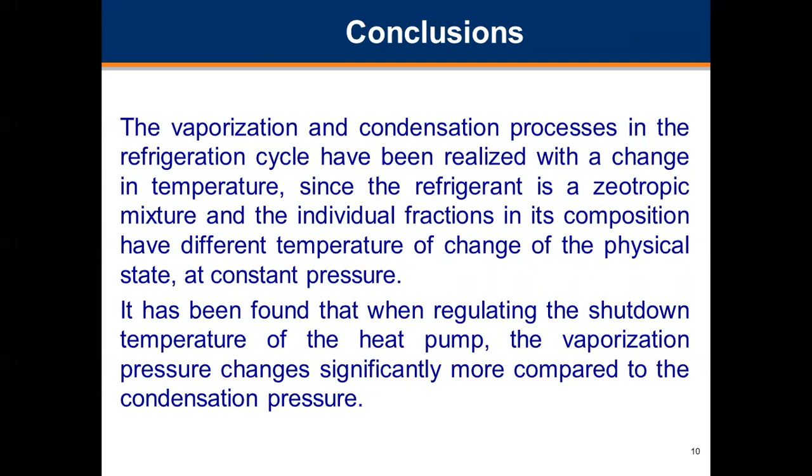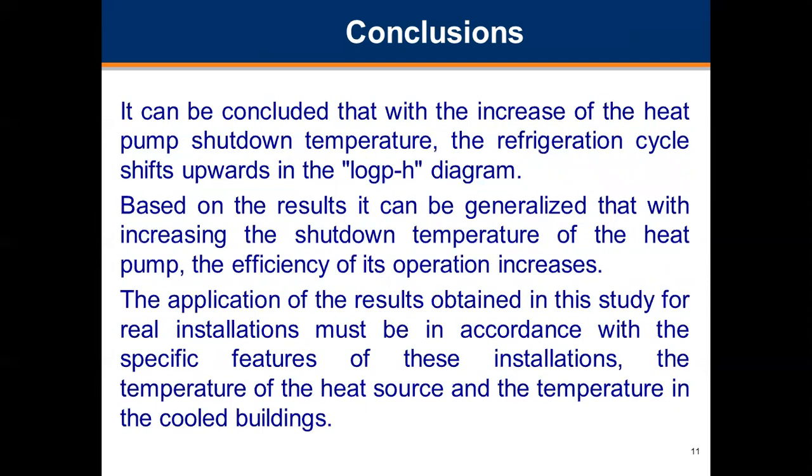It has been found that when regulating the shutdown temperature of the heat pump, the vaporization pressure changes significantly more compared to the condensation pressure. It can be concluded that with the increase of the heat pump shutdown temperature, the refrigeration cycle shifts upwards in the log p-h diagram.